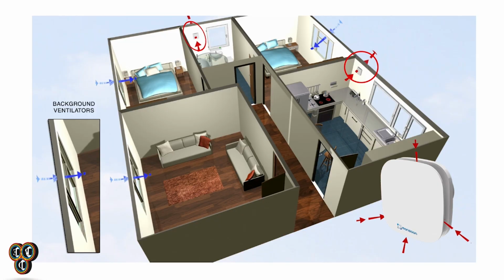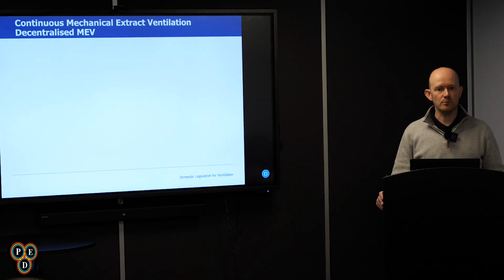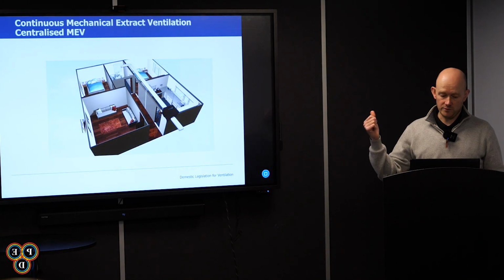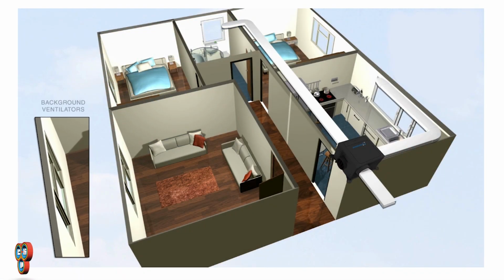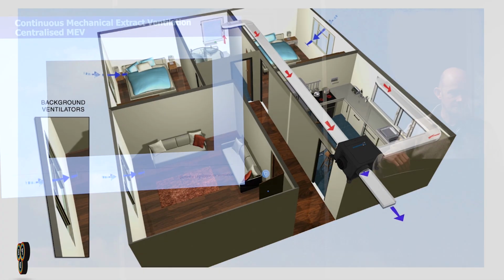Everything's going this way, everything's coming away from intermittent over to this. So intermittent fans are a bit of a dying breed. Another little video on the centralised unit. Same principles again. Centralised unit, ducted, return air through trickle vents, extract from wet areas. This is more of a design product. We would probably recommend, us and all of our other suppliers would recommend coming to them, getting a design done instead of just installing it how you think, because you close up a house and you've got it wrong.